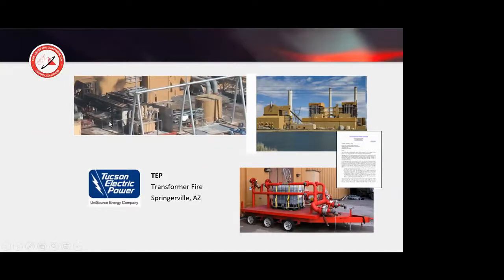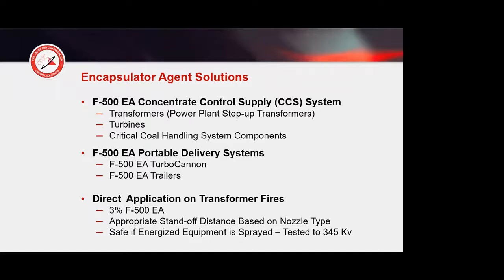So here's a transformer fire at Springerville. They used this unit. They were able to extinguish that in about 45 seconds. So they don't have a fixed system, but they were able to do it. So, you know, the concentrate control systems are for transformer turbines, critical coal handling components. They can be used on lithium-ion battery in the petrochemical industry. So the transformers are not just at power plants, steel mills, refineries, automotive places, anyone who has large power demands, big industrial, pulp and paper mills, paper processing facilities, all have these type of applications.